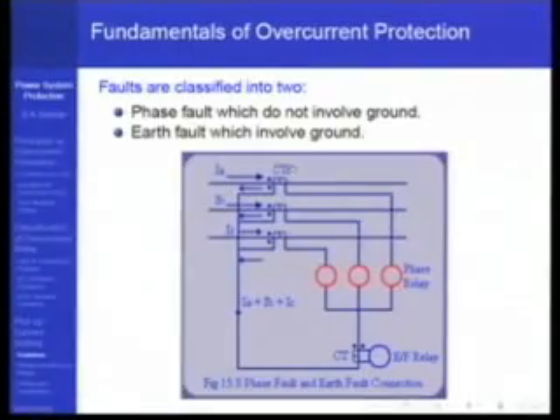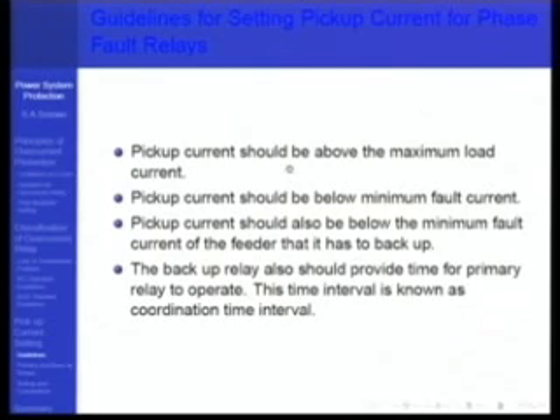Okay, now let's look at some guidelines for setting pickup relays for phase fault relays. So pickup current should be above the maximum load current, that is understood, because as I said, phase relays are working on positive sequence current, and normal load current is also a positive sequence current, so it should pick up above that. Pickup current should be below minimum fault current, that is also your expectation because you want no fault to go unprotected. Pickup current should also be below the minimum fault current of the feeder that it has to back up, otherwise backup responsibility will not be handled correctly.